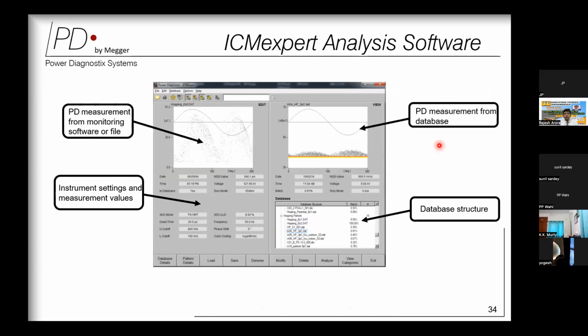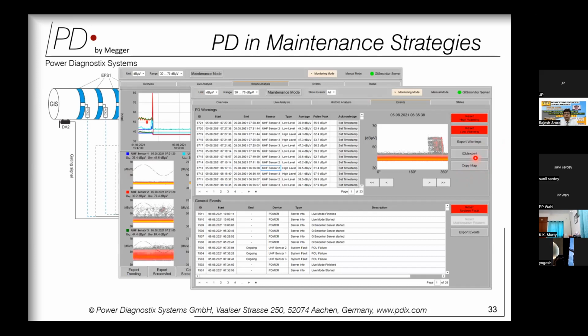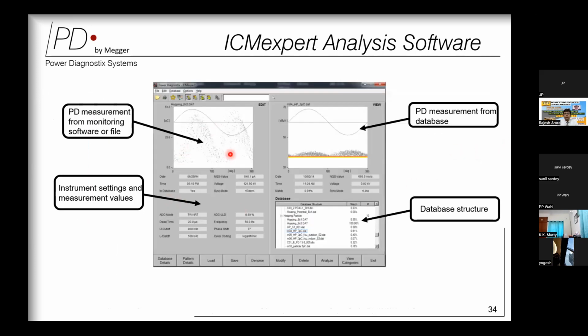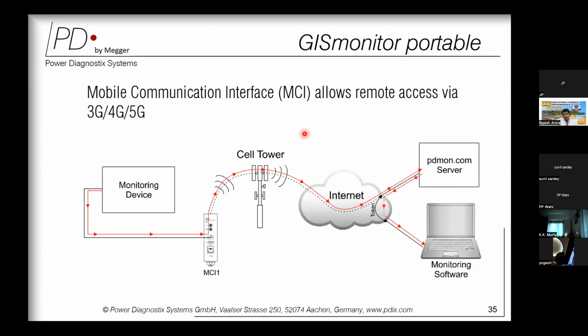Once we have this partial discharge pattern captured, we can see here there is an ICM expert button. Once we press this button, the next software screen is available, where the original PRPD pattern will be captured against the database and the result will be populated with the matching pattern. So if you are a new user or you are not exposed to pattern analysis, there is software to help you which will always be about 95 to 98% accurate in its interpretation.